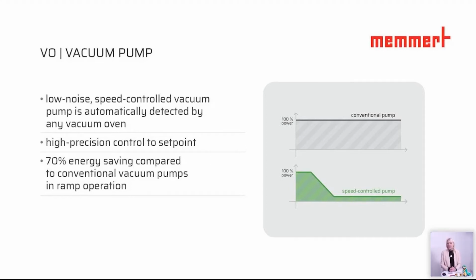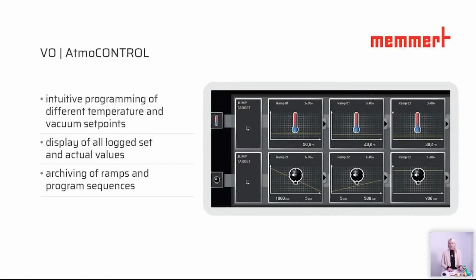And that means, please kindly note, on our vacuum oven, you can do ramping. So we have the digitally controlled ramping for pressure up and down. And we have here additionally the speed controlled pump. And that means by these combinations, we have 70% energy saving compared to a conventional vacuum pump when we operate in the ramp operation. I just mentioned ramp operation. Let's have a look a little bit closer at what this ramp operation actually means. Ramp operation means that we can set different temperature ranges, and we can also set different pressure ranges. So we can go down in steps by the pressure. So it is intuitive programming of different temperature and vacuum set points.